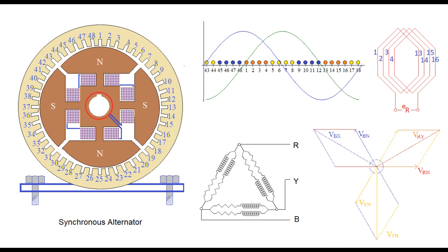The cross-sectional view of the synchronous machine that we see has two pole pairs, so the synchronous speed is 1500 rpm. Since the armature windings have two pole pairs, each pole pair provides one path for a phase. The phases of all pole pairs must be connected in parallel to form a phase. In this way, the synchronous alternator that we are considering now will have two parallel paths in each phase of the armature windings.